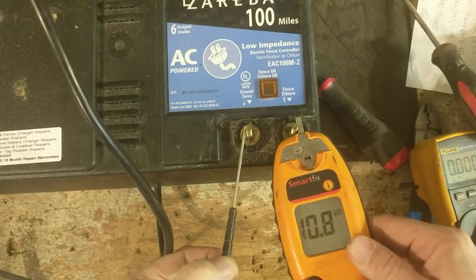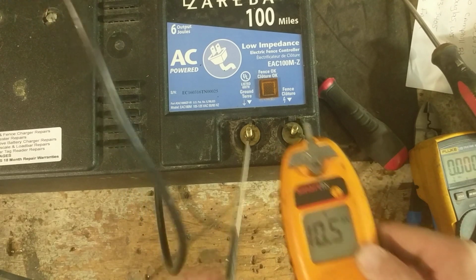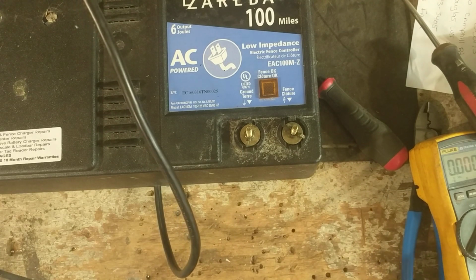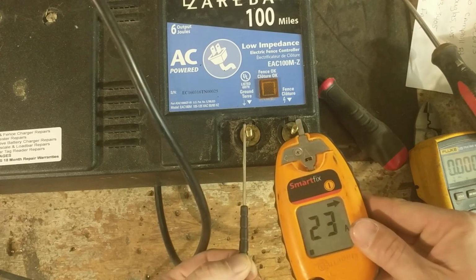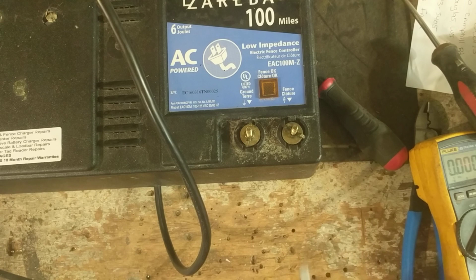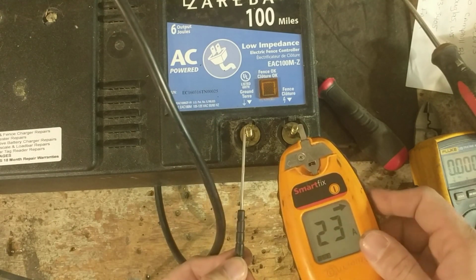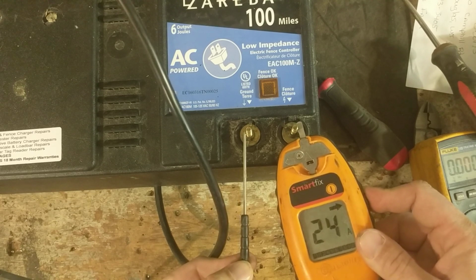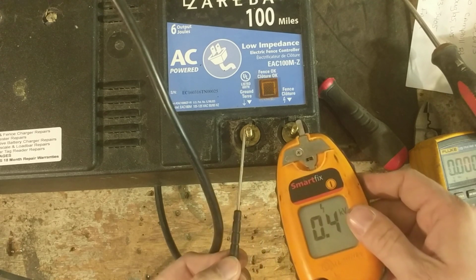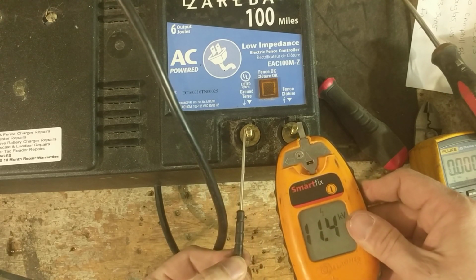It's reading 11 point something, almost 10,000 volts. And we'll go to amps... 24 amps. So that tells us the amp feature, the fault-finding feature on this tester, is working, and of course the kilovolt reading is working as well.